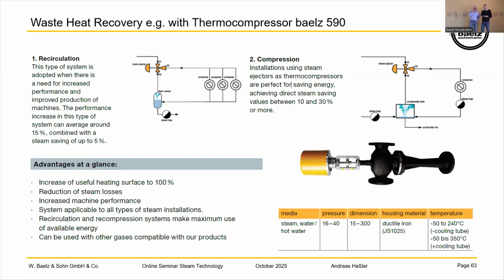I guess, yes. That's also a very good question. It depends also on the conditions. In normal case, the ratio is not this big, because you have to suck the lower pressure with the motive steam. I would say it depends on what is important for you. Is your outlet steam important or what you want to suck important? I would say 1 to 5, 1 to 10, something about that. But also individually. When you have a higher motive steam pressure, the difference between the suction pressure and the outlet pressure should not be too high. When this one is too high, this valve will also not work.